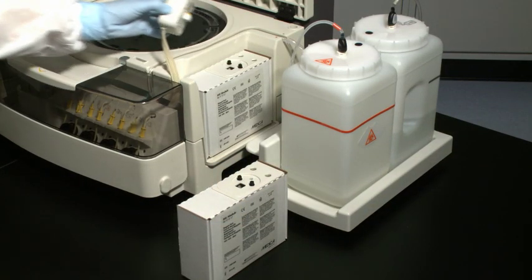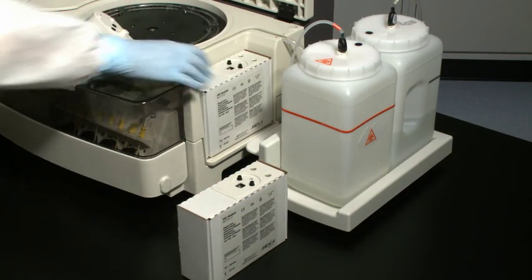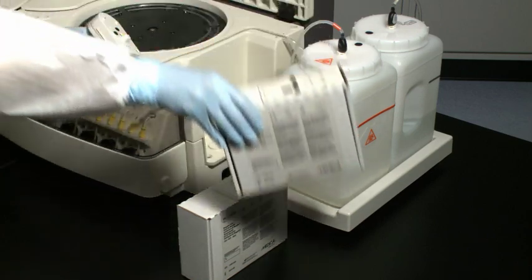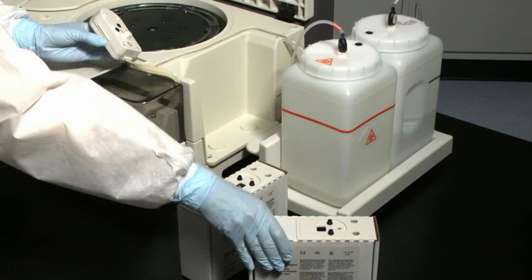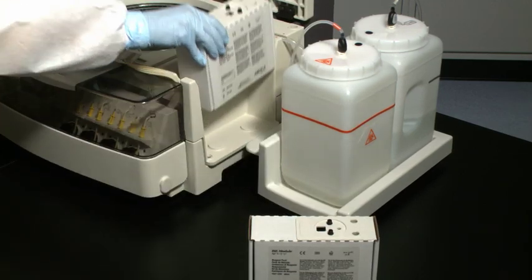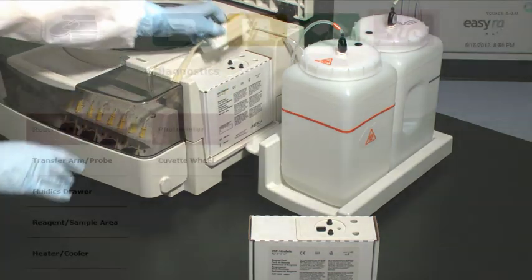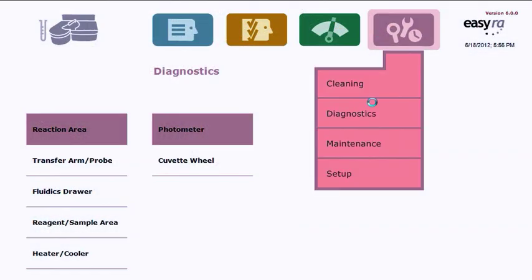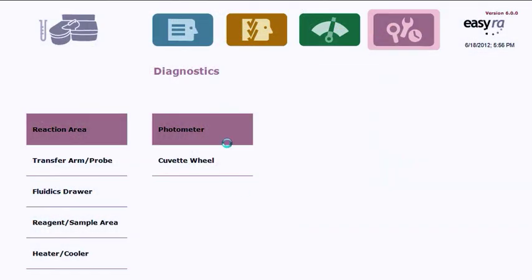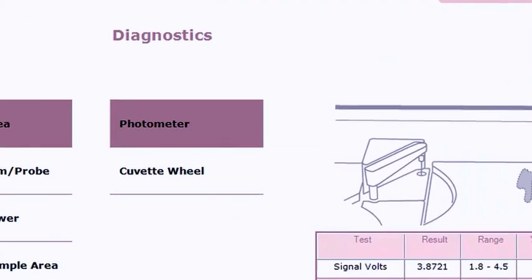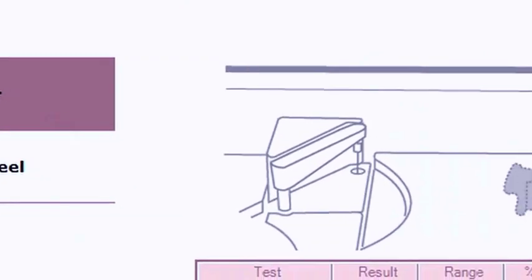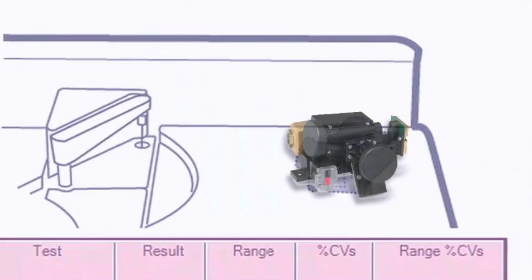ISE reagents are contained in a convenient, disposable reagent pack. The photometer's xenon flash lamp has a five-year use life with no required maintenance and no bulb to replace. That means no analyzer downtime.